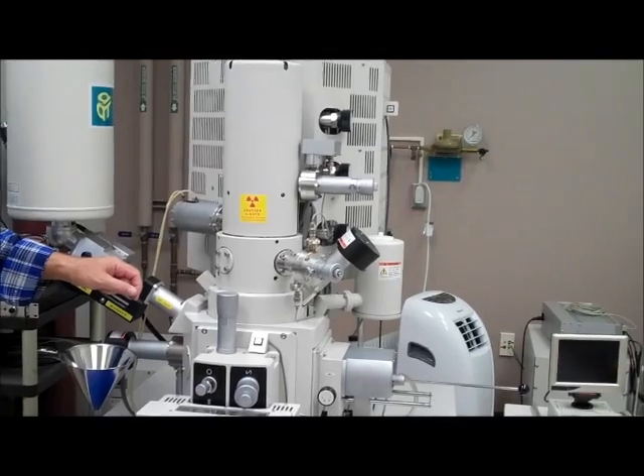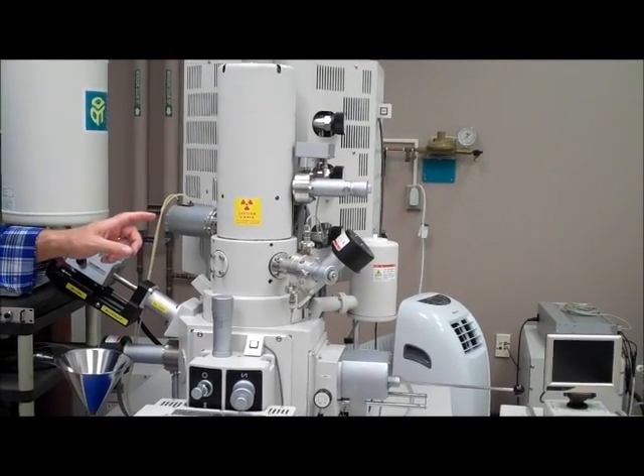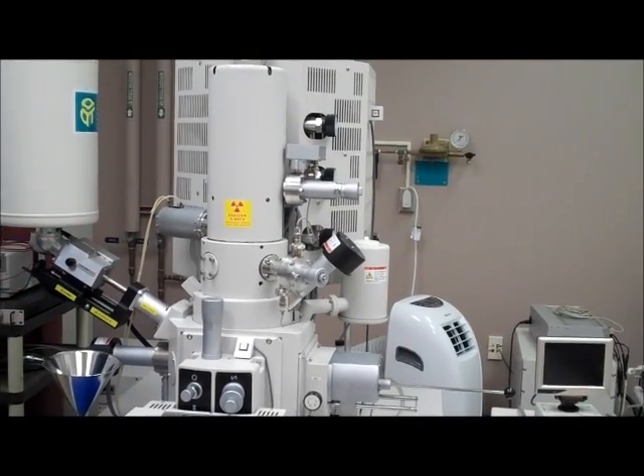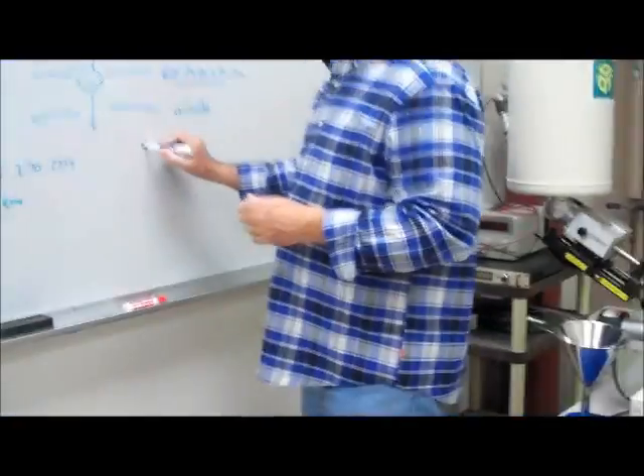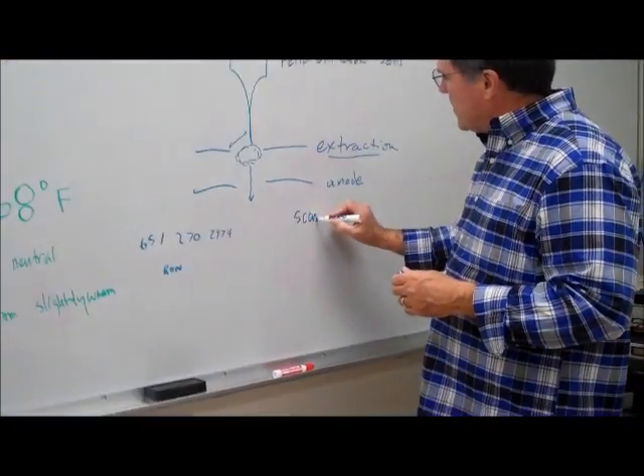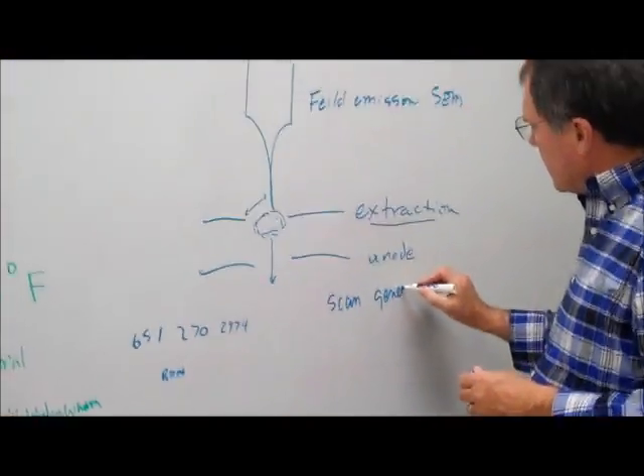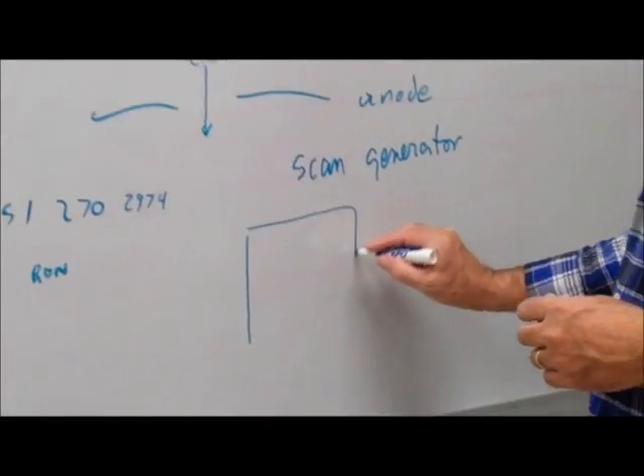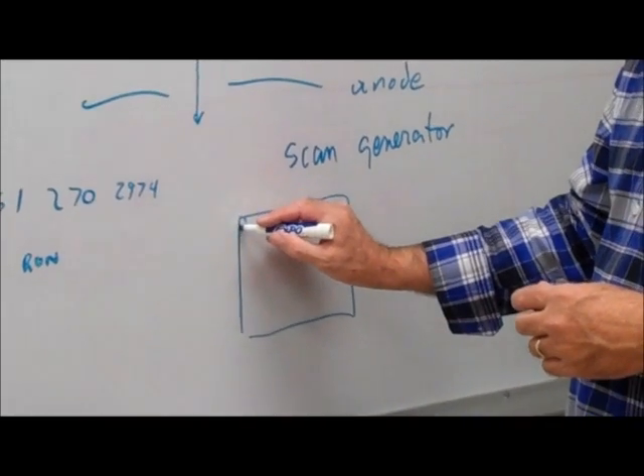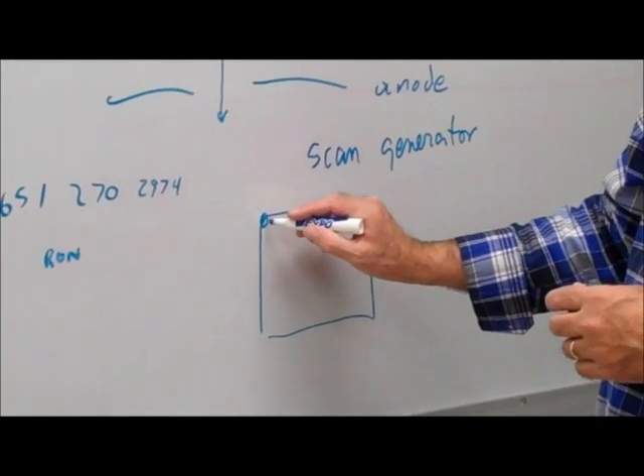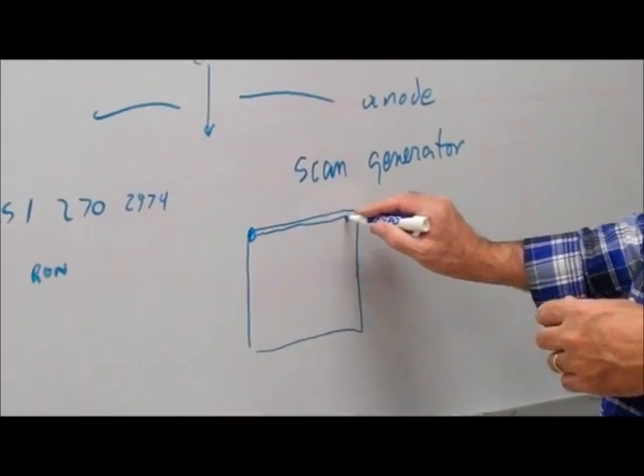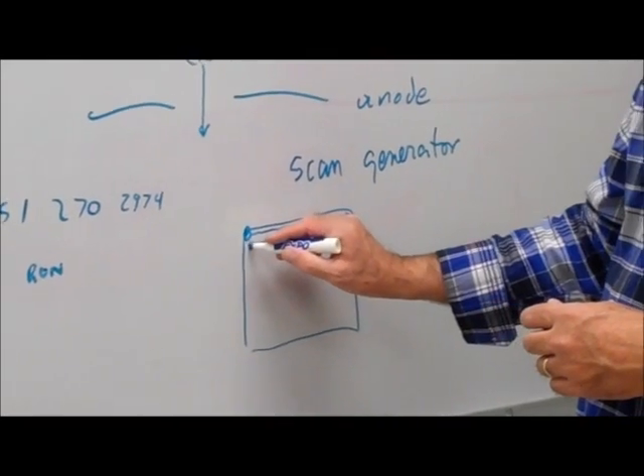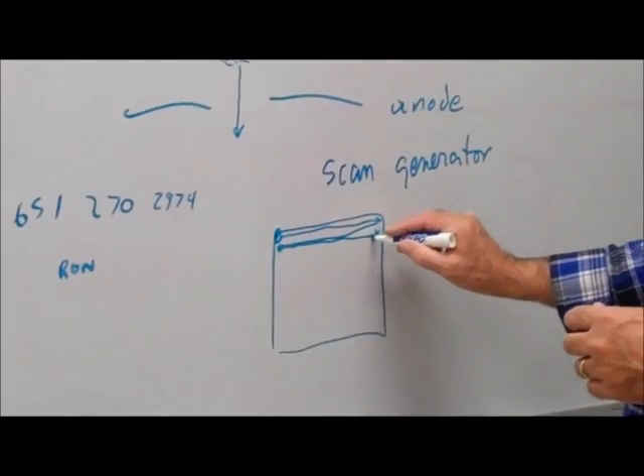And then the scanning part of it comes from a device called a scan generator. And if you look at the surface of the sample, the scan generator forces the electron beam across the sample, and then down one line, and then across the scan.